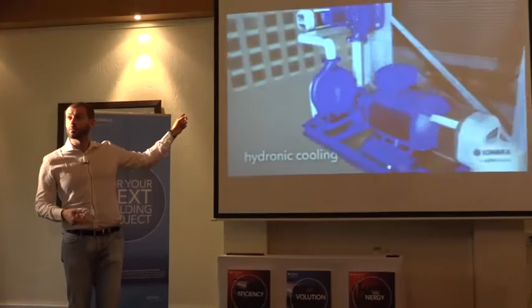So actually an inline pump can be installed in every position, but the standard configuration has about 15 different possible installation solutions. What we always suggest to avoid is installation that isn't exactly perpendicular, so diagonal installation. We strongly try to avoid that—this is an end suction pump, so it should be installed vertically. That's perfect.